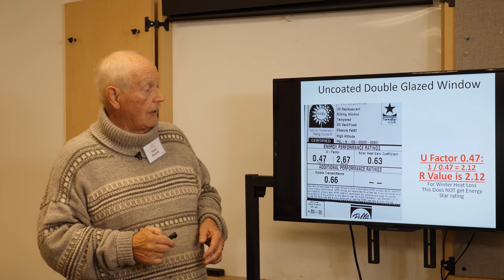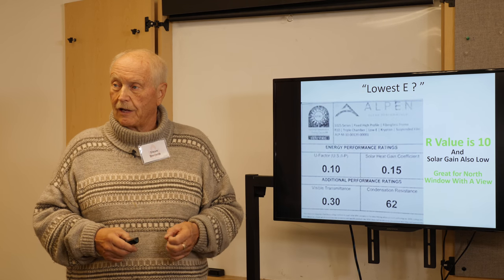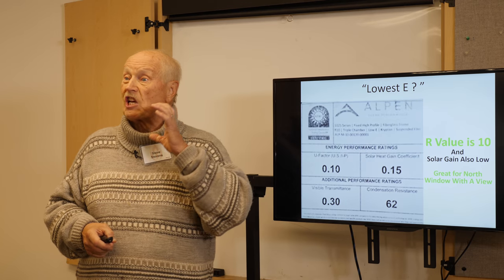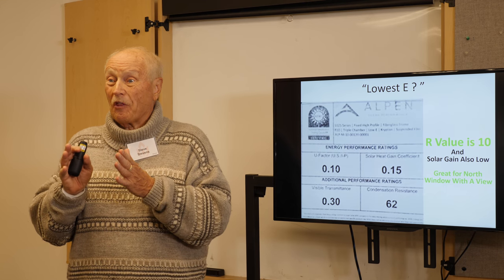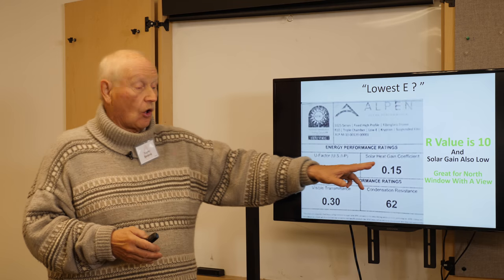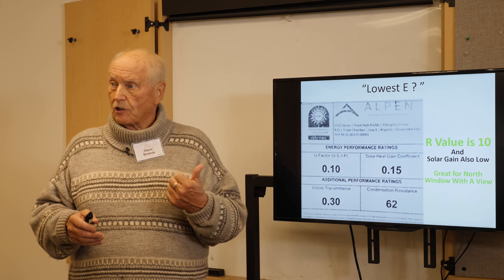And an example of how far it's gone is an Alpen that John has one of in his house. And the U factor is 0.1, which says the R is 10. It's better than a 2x4 wall with a batt of fiberglass. The window's better than the wall. I mean, that's amazing.